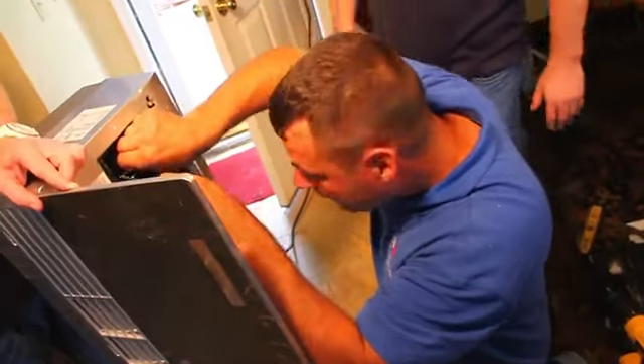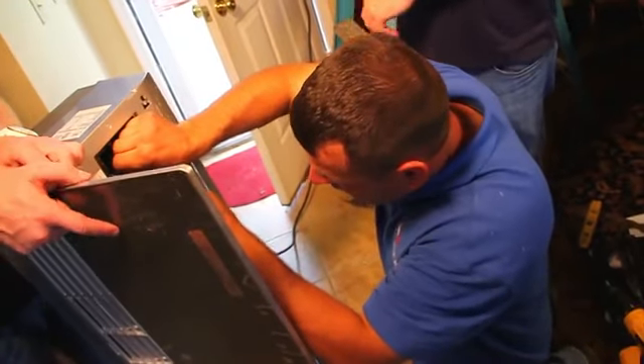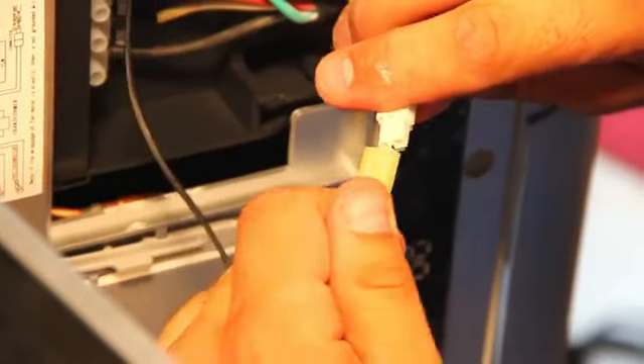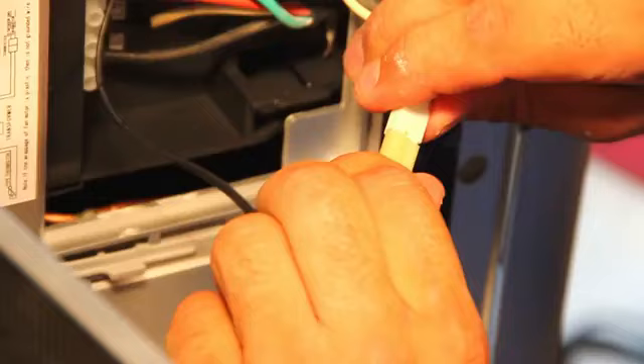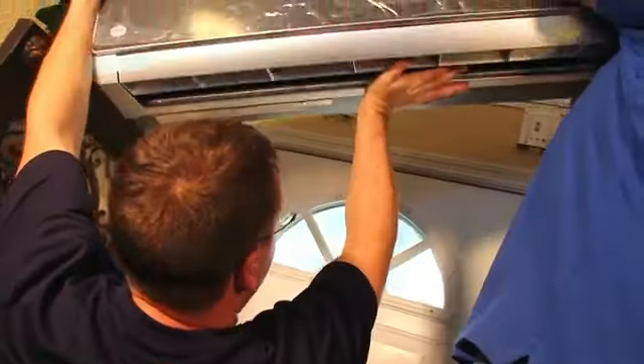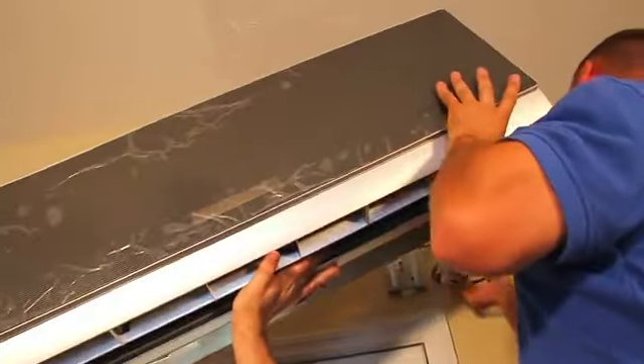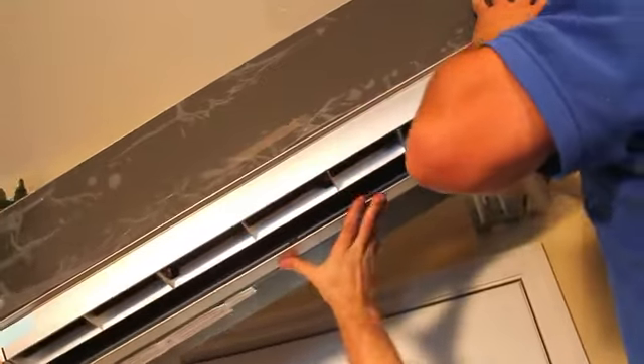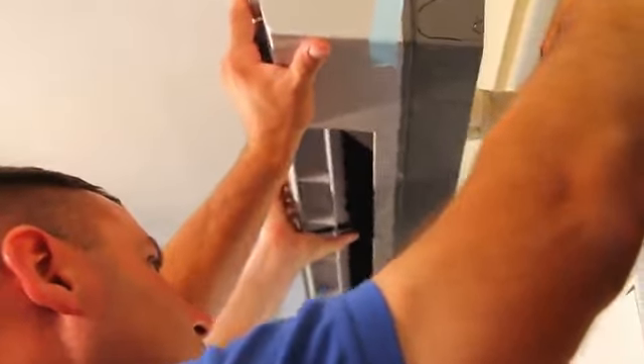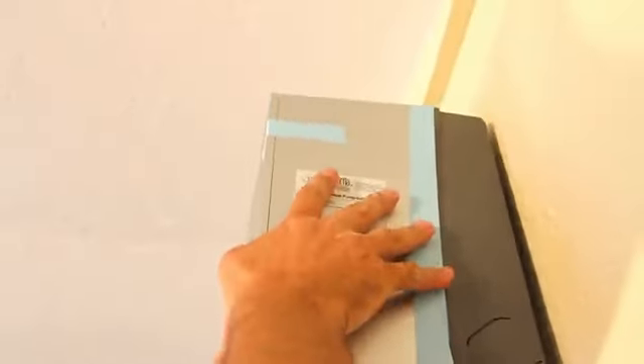Now, once the wall mount is ready, the condensate tube is attached, the refrigerant line is secure, plugs are installed, and the electrical cable has been run through, you are ready to mount the interior unit on the wall. Lift the unit into place, making sure that the tube, line, cable combination pushes smoothly through the opening you drilled.